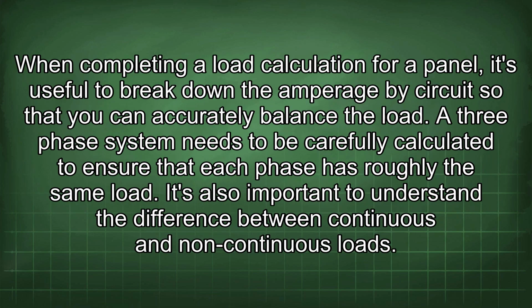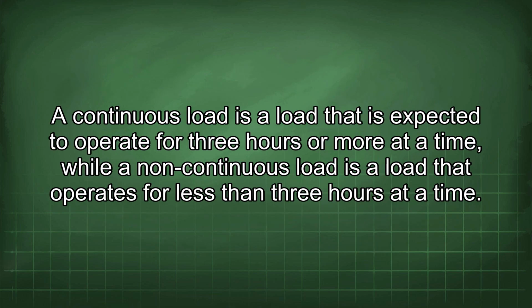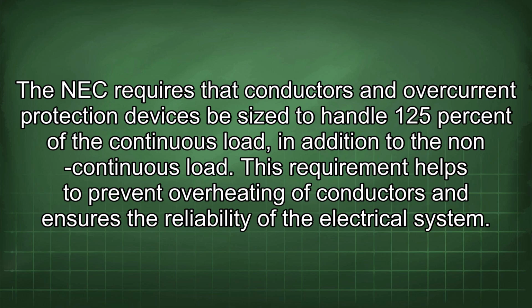When completing a load calculation for a panel, it's useful to break down the amperage by circuit so that you can accurately balance the load. A three-phase system needs to be carefully calculated to ensure that each phase has roughly the same load. It's also important to understand the difference between continuous and non-continuous loads. A continuous load is a load that is expected to operate for 3 hours or more at a time, while a non-continuous load is a load that operates for less than 3 hours at a time. The NEC requires that conductors and overcurrent protection devices be sized to handle 125% of the continuous load, in addition to the non-continuous load. This requirement helps to prevent overheating of conductors and ensures the reliability of the electrical system.